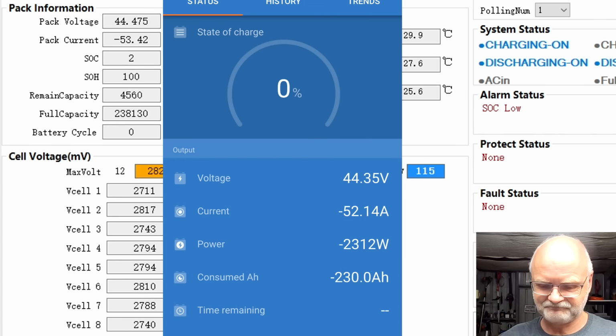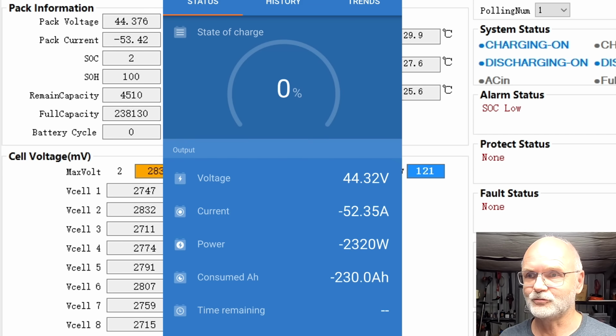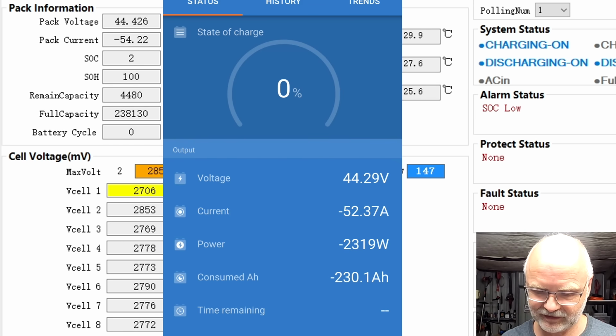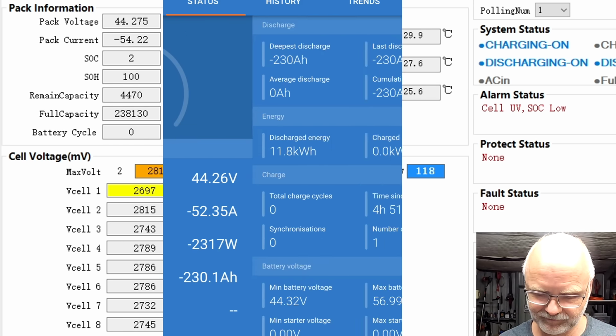230 ampere hours. We have reached the rated capacity of this battery. 11.8 kilowatt hours, so we are a little bit over rated. So we're getting a low voltage alarm, cell under voltage alarm now for single cells, and we also have a pack under voltage alarm at 44 volts now. Pack under voltage, cell under voltage, and low state of charge. Wow. Just alarms. Battery is still going.